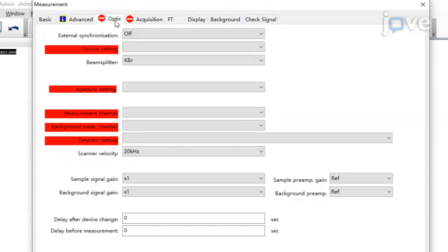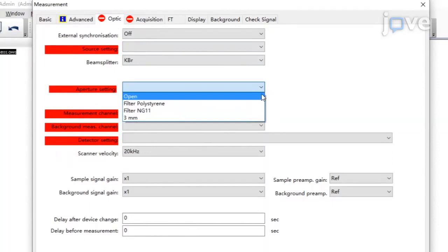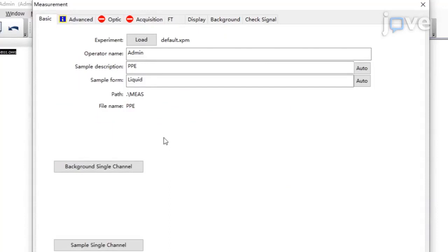Now, click the Optic tab. Click the Aperture setting drop-down list and select the same value used to acquire a sample spectrum. Then click the Basic tab. Click the Sample Single Channel button and place the sample into the optical path of the spectrometer to measure the sample spectrum. Define the sample description and sample form in the particular entry field.